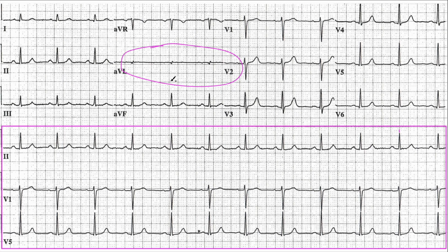This is significant. And first you want to rule out any mechanical issues. So if you've ruled out your electrodes and they're working fine and it's still looking the same way, you've got to double check your wires. If your wires are fine and it's still looking the same way, you've got to check your machine. And let me go back to the electrodes, all of the electrodes, so not just the left arm, right? You want to check the right arm and the left leg as well. So double check everything.